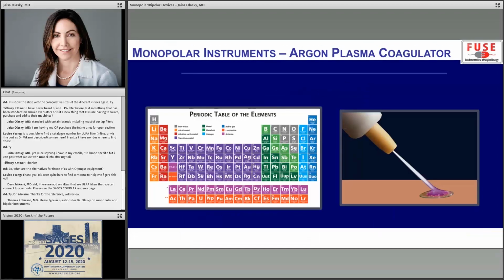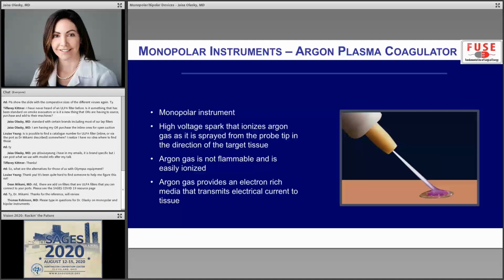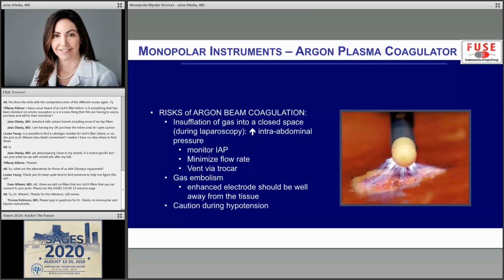So for monopolar instruments, another version, which you don't see as often, is the argon plasma coagulator. Essentially it's a monopolar instrument. You do need a dispersive electrode, and you're using argon gas as the transportation for those electrons to get the current to the tissue. So it's highly efficient, and it's not flammable. From those standpoints, it can be very helpful. I see people use it a lot for splenic bleeding or liver bleeding. Those are the most common scenarios because it's very good at getting that surface fulguration without a lot of risk of stray energy.